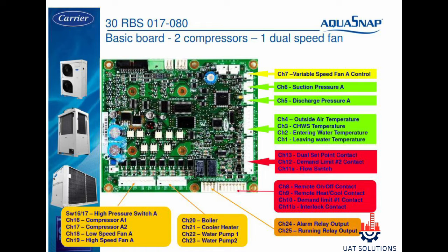Channel 11A is used for the flow switch. Remote on/off contact is connected on channel 8. Remote heat or cool contact is on channel 9. Demand limit number 1 is on channel 10. Interlock contact is connected on channel 11B. Boiler command is connected on channel 20. Cooler heater is connected on channel 21. Water pump 1 and 2 are connected on channels 22 and 23.